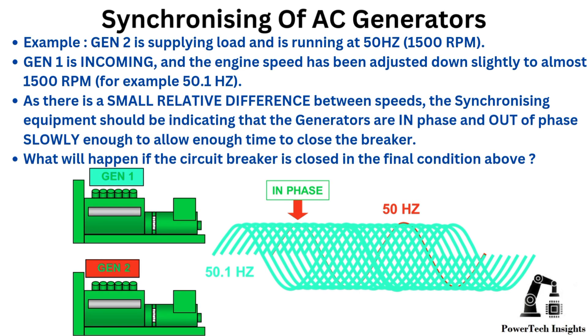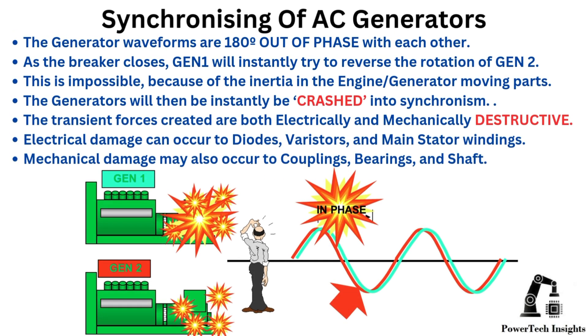What will happen if the circuit breaker is closed when the generator waveforms are 180 degrees out of phase with each other? As the breaker closes, Gen 1 will instantly try to reverse the rotation of Gen 2. This is impossible because of the inertia in the engine/generator moving parts. The generators will then instantly be crashed into synchronization. The transient forces created are both electrically and mechanically destructive. Electrical damage can occur to diodes, varistors, and main stator windings. Mechanical damage may also occur to couplings, bearings, and shaft.